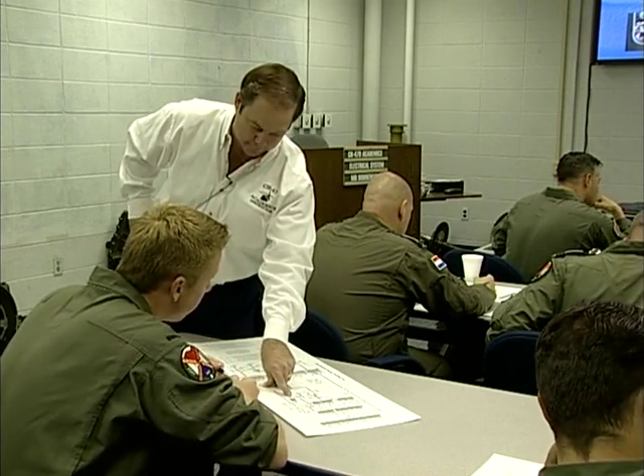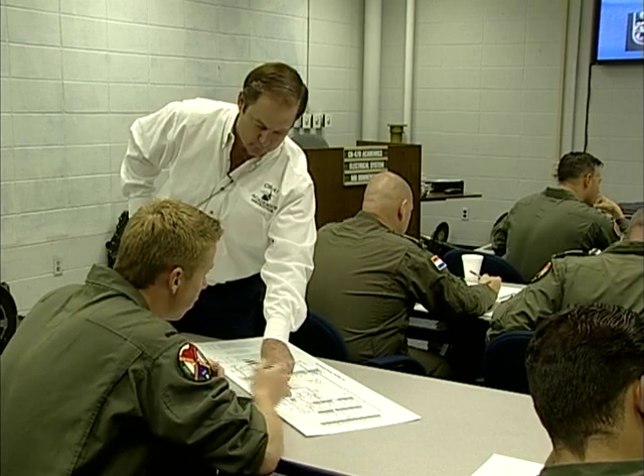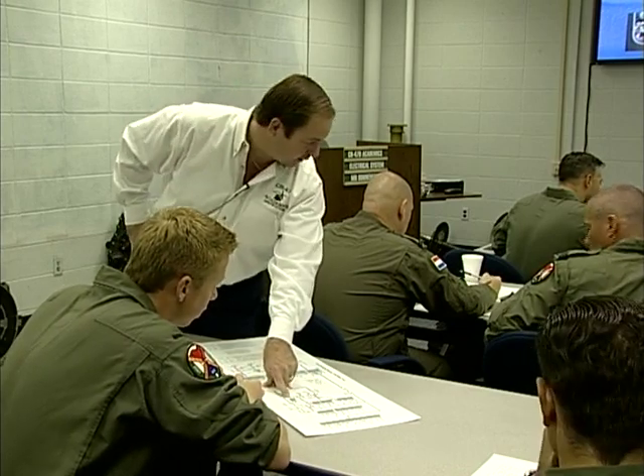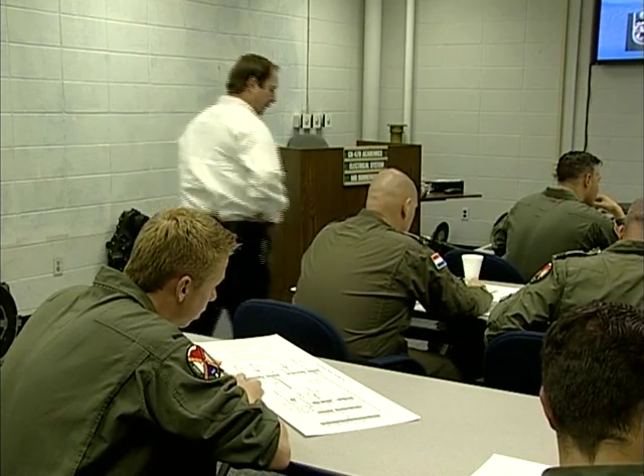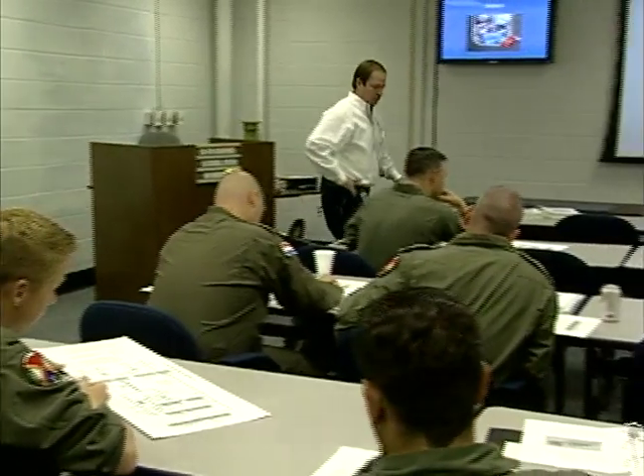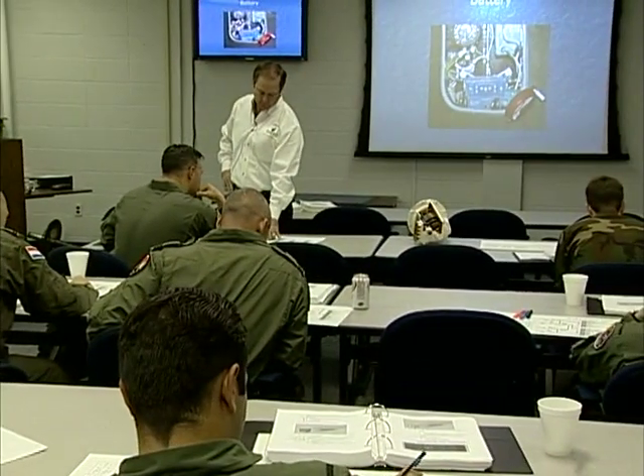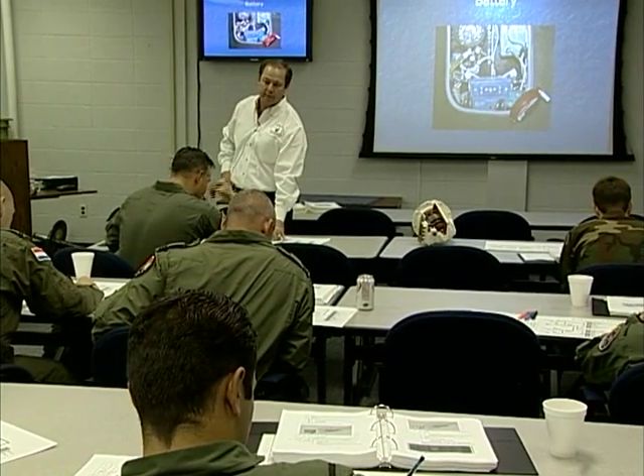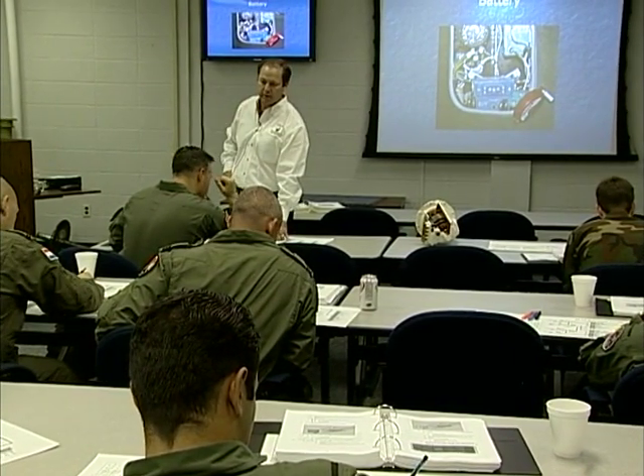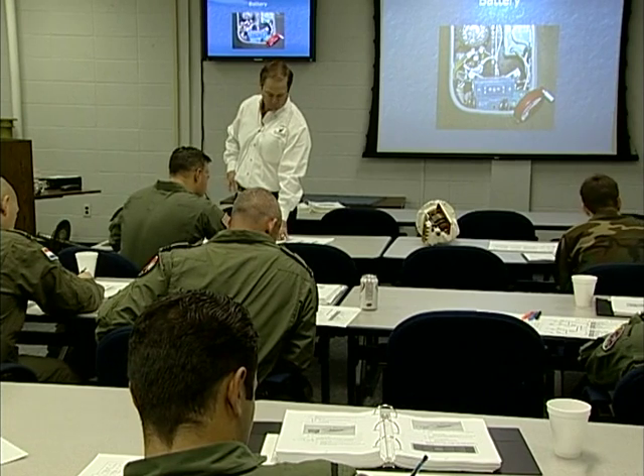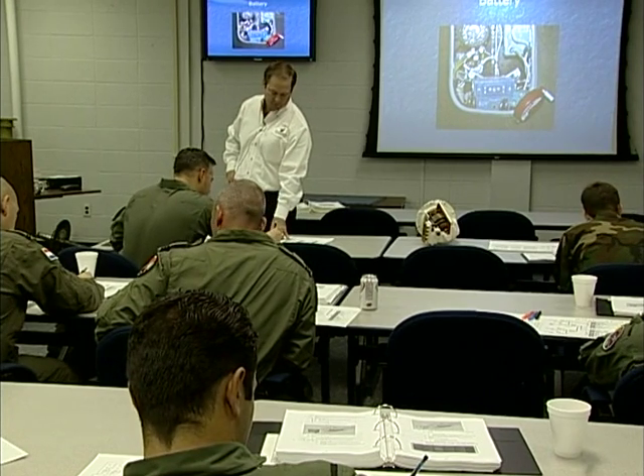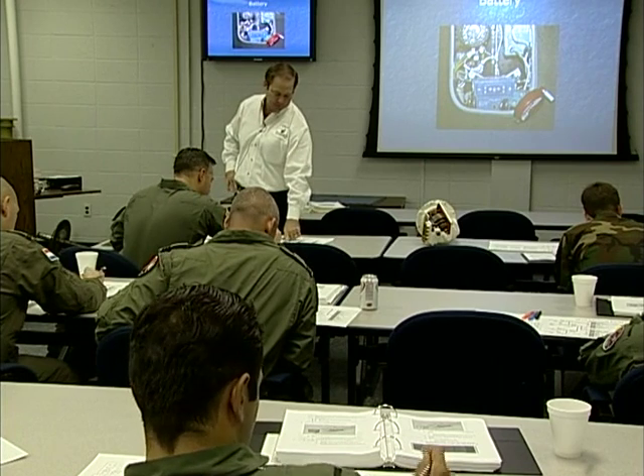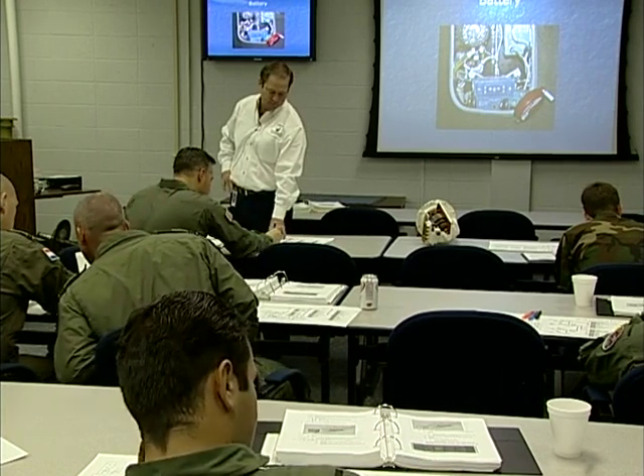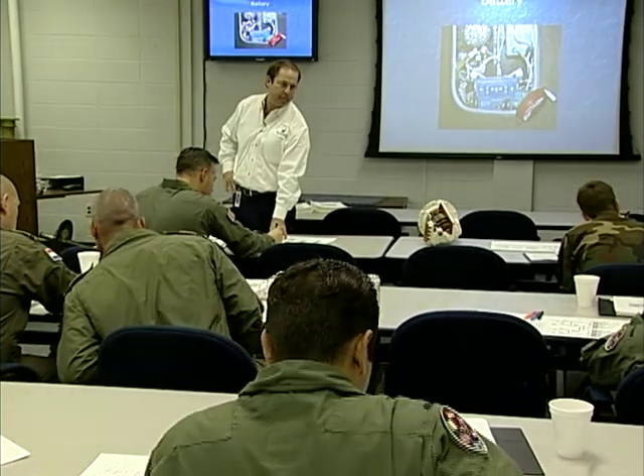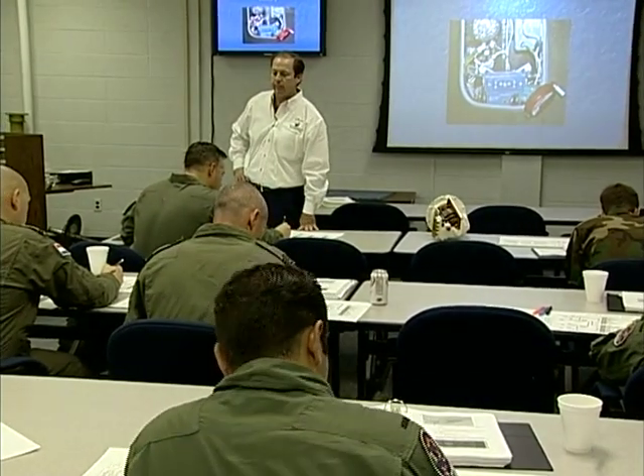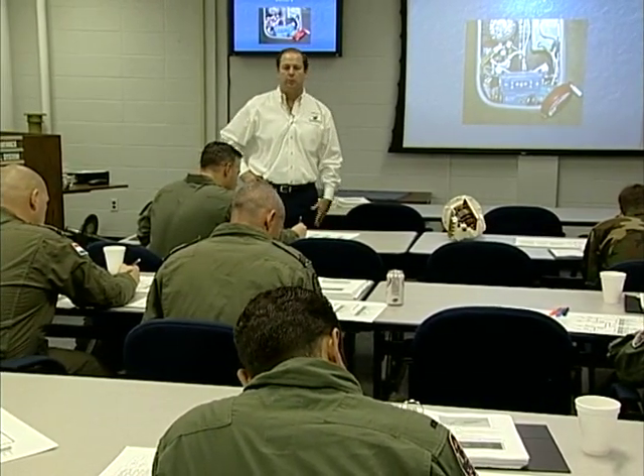We're gonna fix that one. You're right, you're 100% correct, that would make me wonder. Yep, this schematic is not perfect, gentlemen. You're 100% correct, where it says switch battery bus, above it there should be a solid black line too. If you want to put in that solid black line, that's okay. What they were using is the fact that through the essential bus relay and the switch battery bus relay, they just forgot to carry it through.